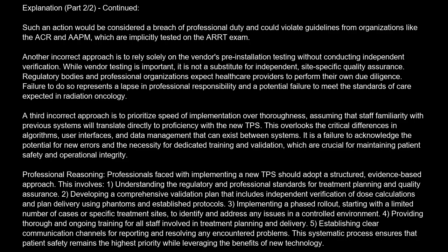Another incorrect approach is to rely solely on the vendor's pre-installation testing without conducting independent verification. While vendor testing is important, it is not a substitute for independent, site-specific quality assurance. Regulatory bodies and professional organizations expect healthcare providers to perform their own due diligence.